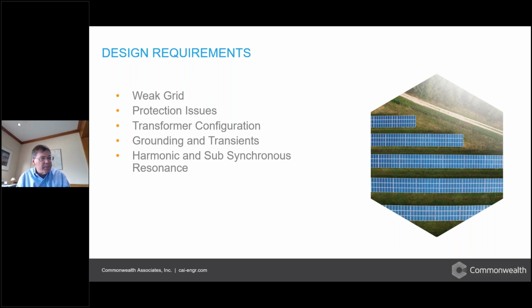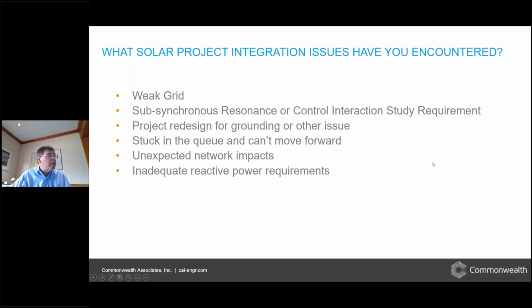There's also the idea of subsynchronous control interactions. So if you look at the control of a typical solar inverter, there are 40 different settings for that inverter. Some of them relate to protection. An example that comes to mind is the factor K, which is supposed to be set mutually by the transmission provider and the inverter manufacturer. We see that sort of detail missing, and again, the consequences of that will come up.